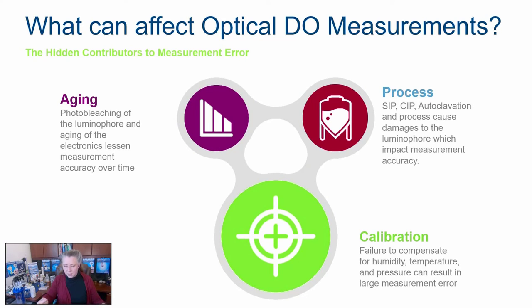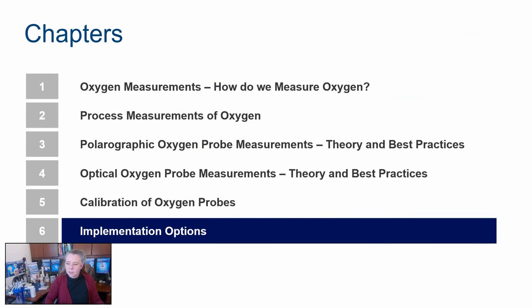It happens. Your process. You're going to do autoclavation. You're going to do steam in place. You're going to culture critters. They're going to make things. Those also will cause aging and contributions to your measurement error. You could quit and go farm and then you don't have to worry about this. But other than that, it's not something you can really change. Calibration is the only thing you have any control over. And the best practices you can do in calibration allow you to do the biggest contribution to minimizing error in the measurements. It's the only thing you have control over. So use that. Now, one last thing quickly before I go into it.